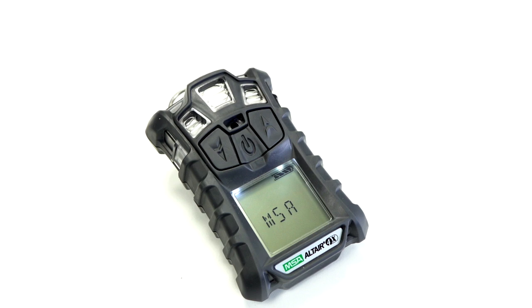The display then goes on to show the manufacturer name, the product name, the software version, the running sensor discovery, the type of combustible gas, the measurement units shown for toxic gas, alarm set points for the low alarm and high alarm, short-term exposure limits, the time-weighted average work exposure limits, calibration values, the current time and date, and lastly, the date of the last calibration.